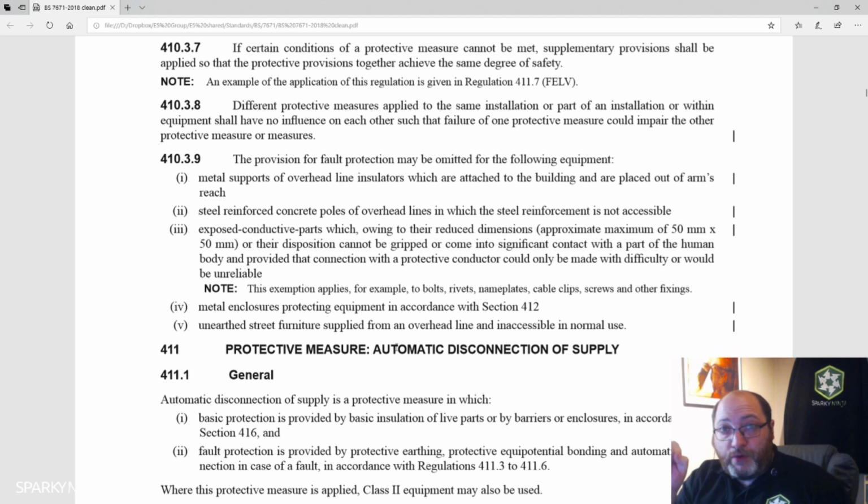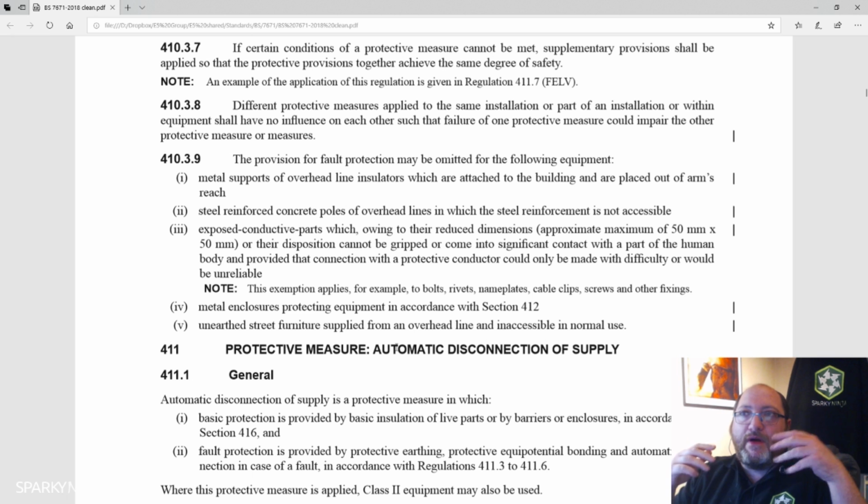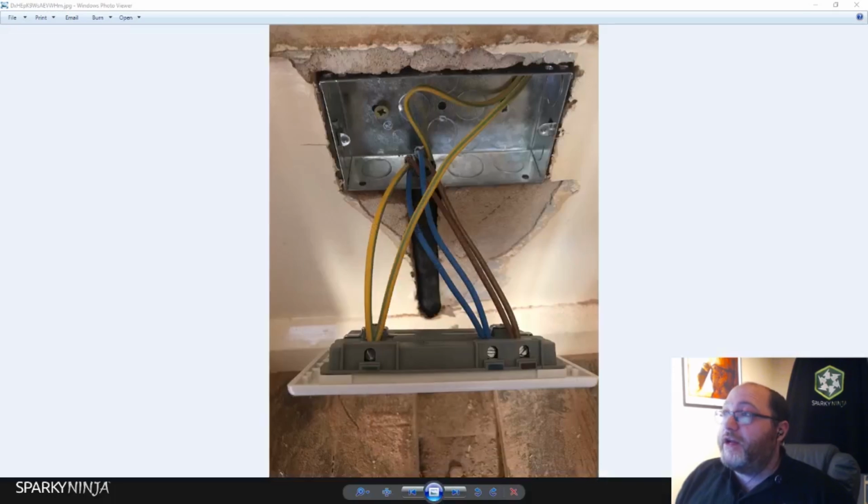I would use the screw in the back box and a fly lead to the socket only if the back box is the wiring system bringing the earth forwards to the accessory. All right, that's my technical interpretation, but as I'd like to repeat, as I said earlier on, I still would do it this way from habit, from considering best practice. Okay, so if you want to say do you, should you, couldn't you, can't you, that's my take on this. All right, but I still would do it this way, it's just habit and I just think it's better practice in my view.